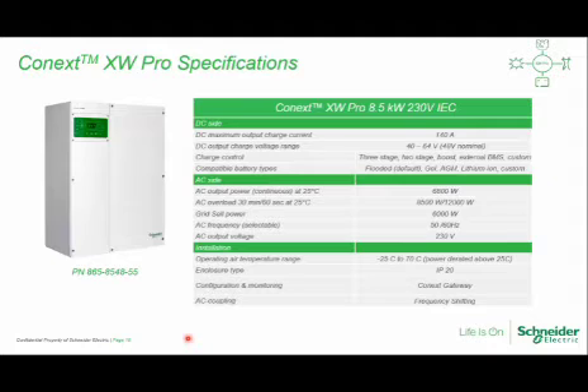Now, the key characteristics of the XW Pro: just like your regular XW Plus 8548, continuous output power is 6.8 kilowatts. The peak it can give for 30 minutes is 8.5 kilowatts, and for 60 seconds it's a 75% increase over regular output power, which is 12 kilowatts. You can sell power back to the grid if possible. There's also an IEC version at 230 volts.